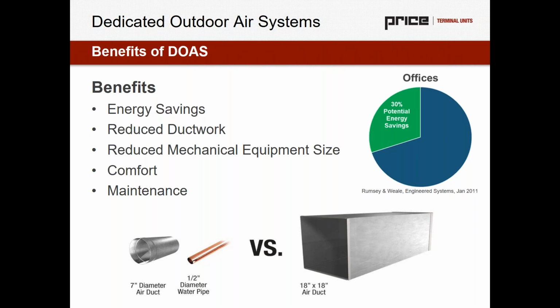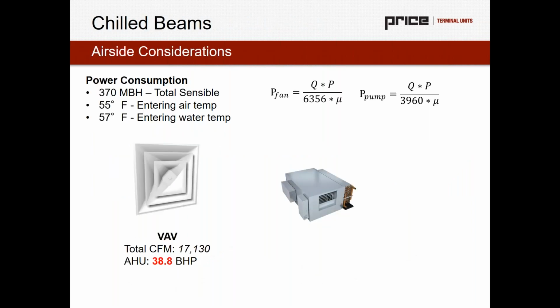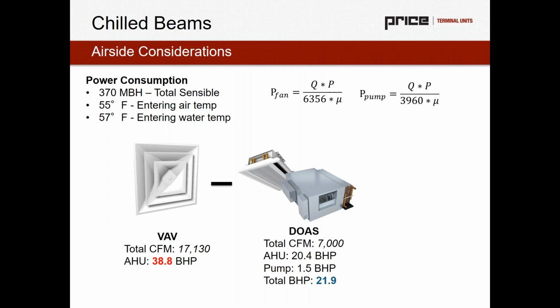That's equivalent to an 18 by 18 inch traditional VAV air duct being compared to a 7-inch dedicated outdoor air system air duct and a 1/2-inch diameter water pipe. Those are equivalent from an energy transportation perspective throughout the system. Because of this, we're getting reduced duct size and reduced mechanical equipment sizing. We're also seeing better comfort in the zone because of the decoupling between humidity and temperature responsibilities. Another thing worth noting here, when we look at this airside consideration, I just want to paint the picture of that energy efficiency.